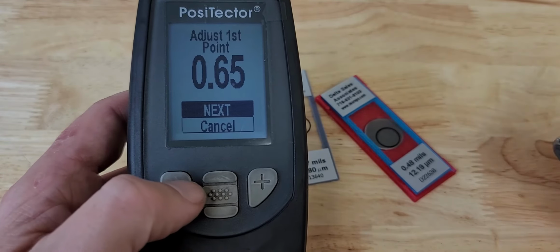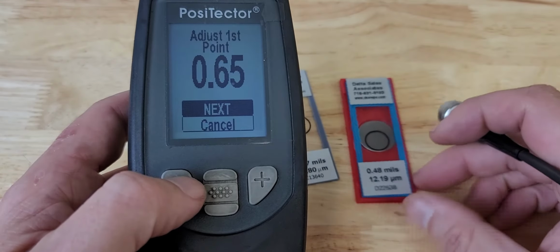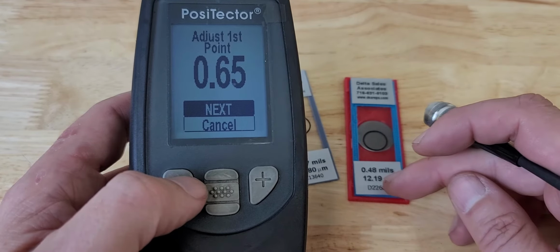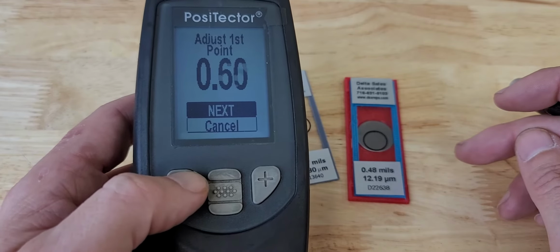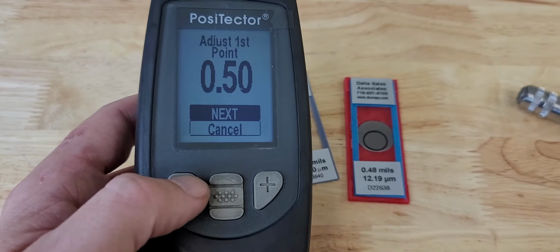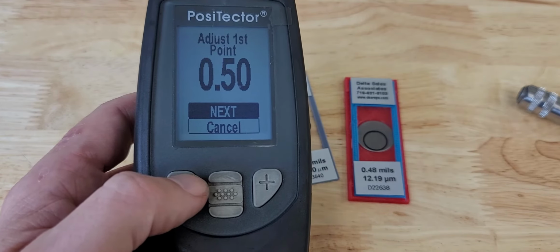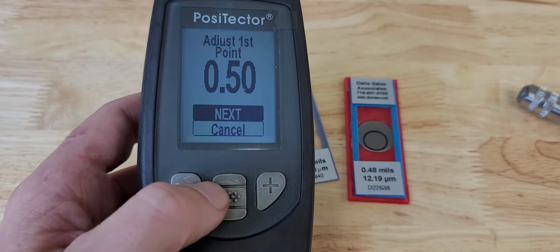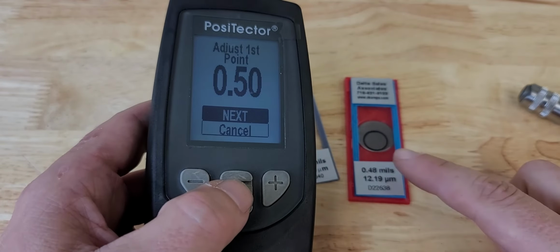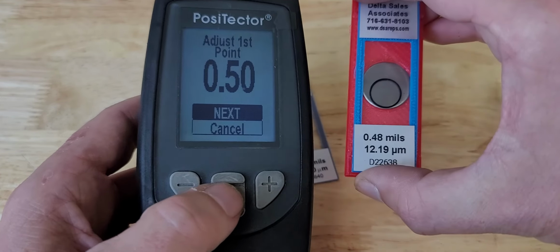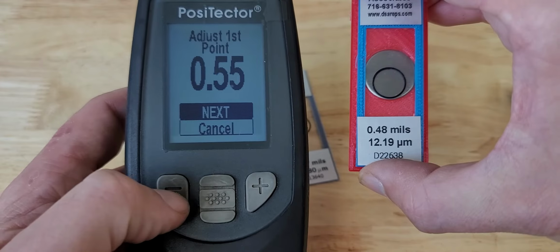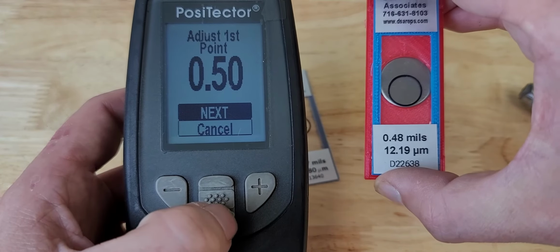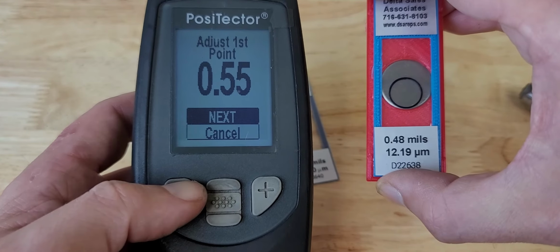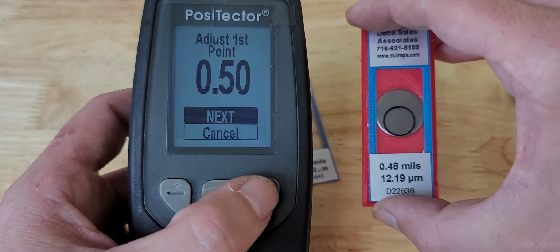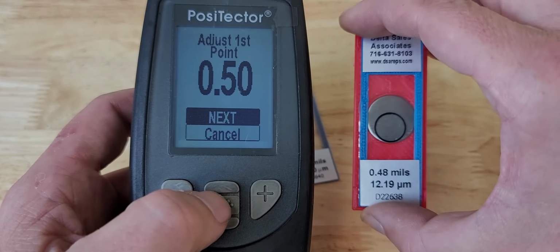Now, we need to adjust this first point. You can see on here our standard is rated at a 0.48, so we need to decrease this to as close to 0.48 as we can get. Typically you would want to set your unit to the exact same number as your standard. However, as you can see, you can only go up by 0.05 increments. So we're going to say that 0.5 is the closest. And we're going to hit next.